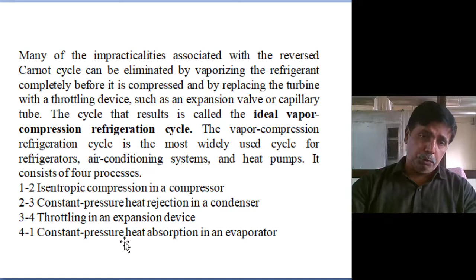So the work input is H2 minus H1, the enthalpy at the end of the work input minus the enthalpy at entry. Heat rejection in the condenser is H2 minus H3, and heat absorption in the evaporator is H1 minus H4. But since it is an isenthalpic process, H3 equals H4, so we get H1 minus H3. Simple. Only the steady flow energy equation we are applying. So 1 to 2 is isentropic compression in the compressor, 2 to 3 is constant pressure heat rejection in the condenser, 3 to 4 is theoretical throttling in the expansion device, 4 to 1 is constant pressure heat absorption. These are the substitutes.